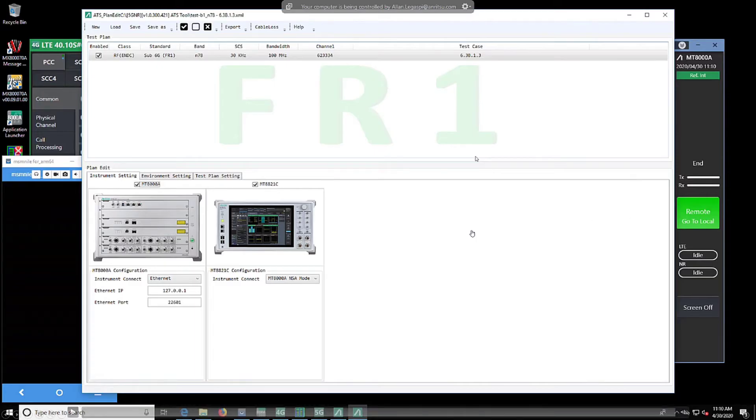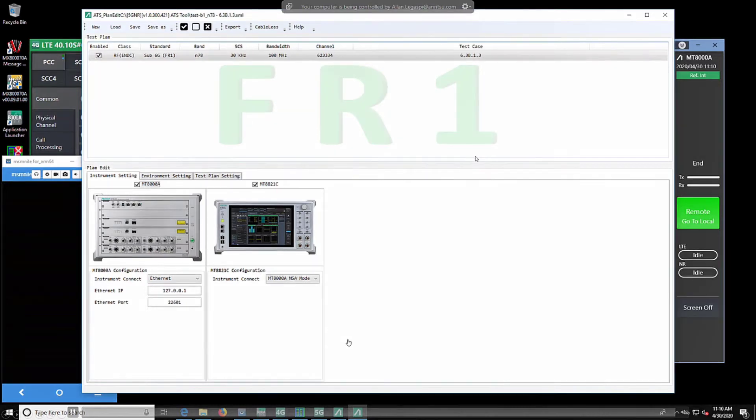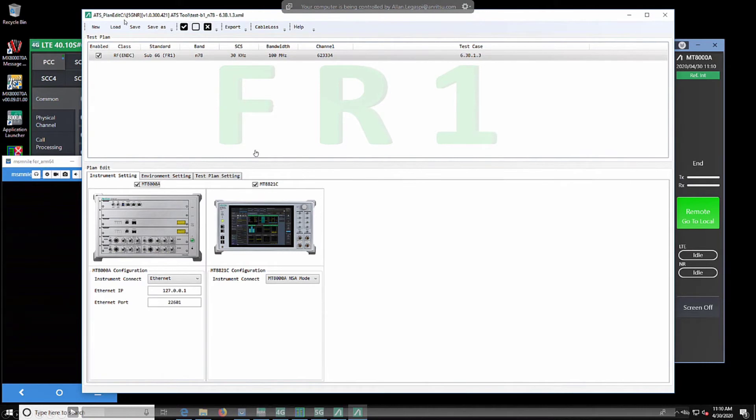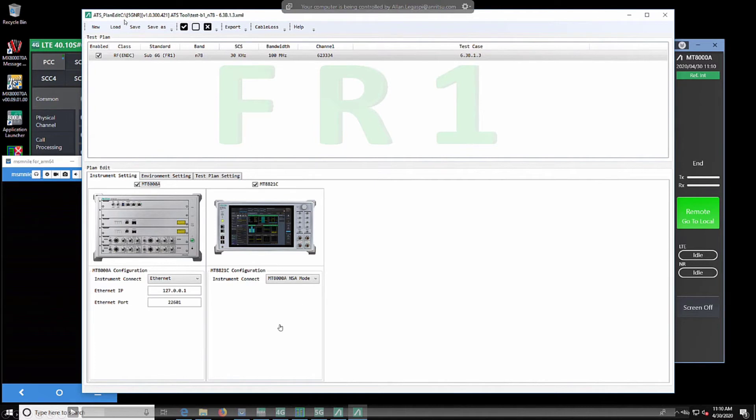Here's a brief demonstration of actually running a test case. We have here the ATS plan editor under the instrument settings where we would set the MT-8000 as well as the MT-8821C to give you MT-8000A non-standalone mode, so you can test within this certain mode.